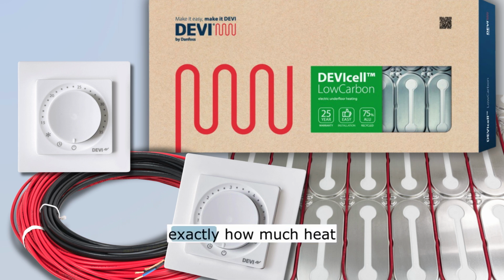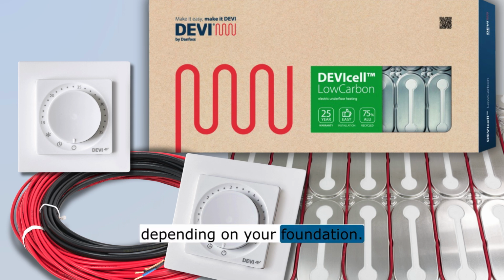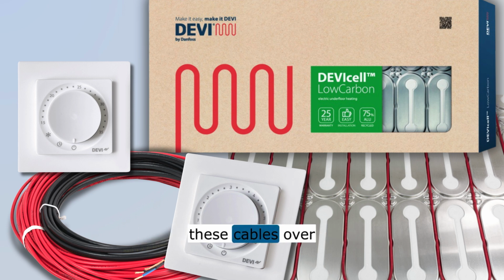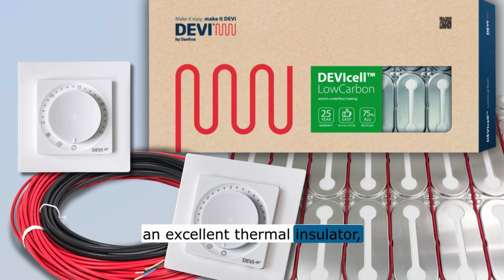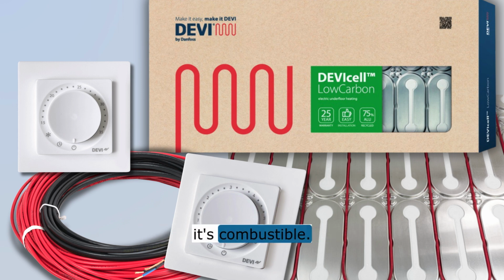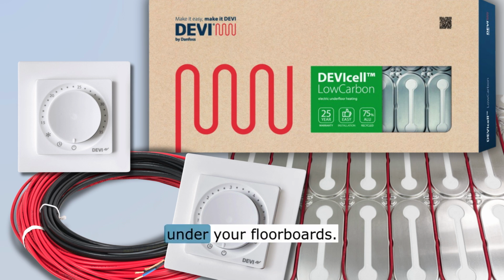The safety rules dictate exactly how much heat you are legally allowed to generate, measured in watts per square meter. And it changes drastically depending on your foundation. It really does. Like if you are laying these cables over a wooden subfloor, your absolute ceiling is 100 watts per square meter. Right, because wood is an excellent thermal insulator, but more importantly, it's combustible. Obviously. So if you pump 150 or 200 watts into wood, the heat doesn't dissipate quickly enough, it gets trapped, and the structural integrity of the wood degrades over time, creating a very real fire hazard hidden under your floorboards.